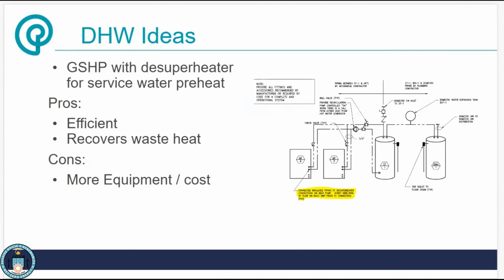On the next one, I've got just two DHW ideas that I've pulled out that were uniquely combined with mechanical systems. So one of them here is from one of the non-res projects earlier that already had a ground source heat pump system going on, so water to water. And they're using a desuperheater, which recovers heat on the ground loop side of that to preheat some of the water, as well as the heat pump itself is heating the water in this preheat tank. And then there's an electric resistance water heater as a booster.